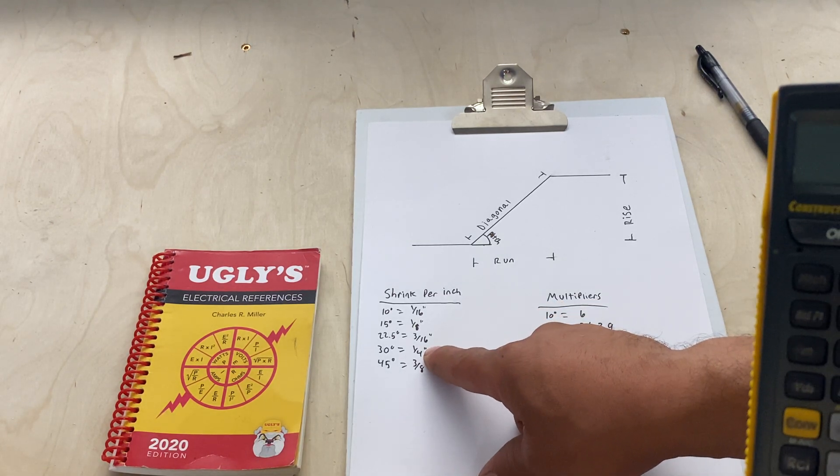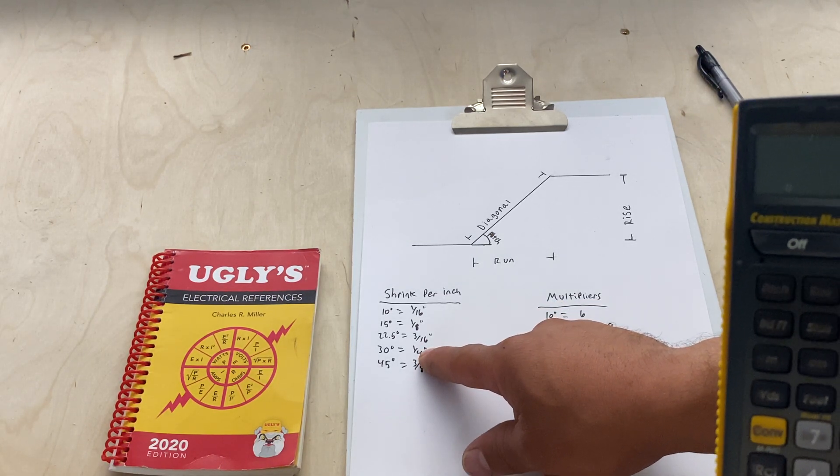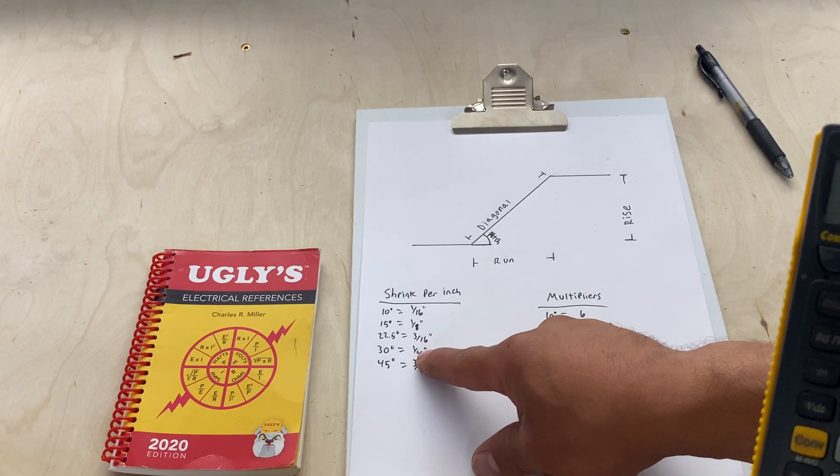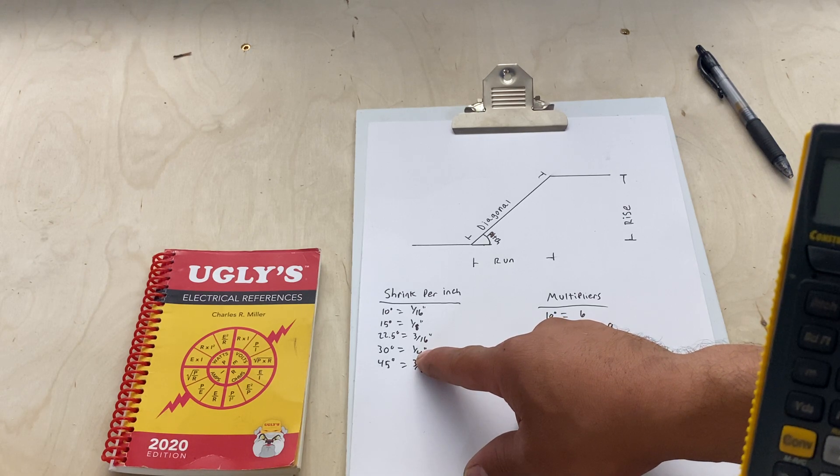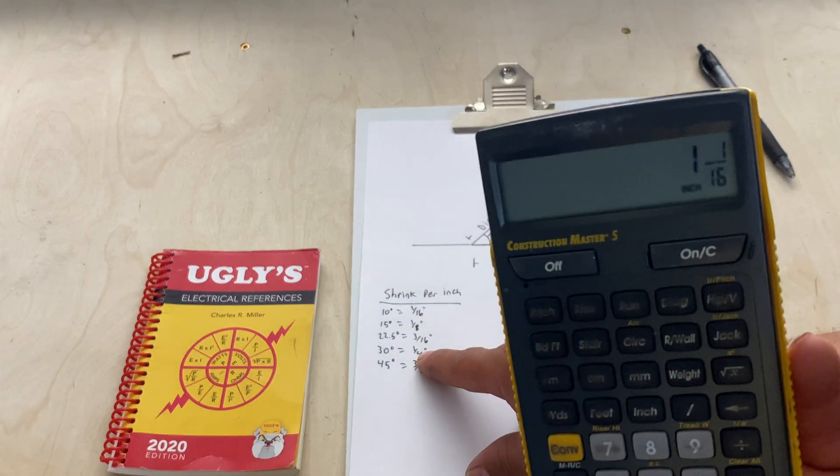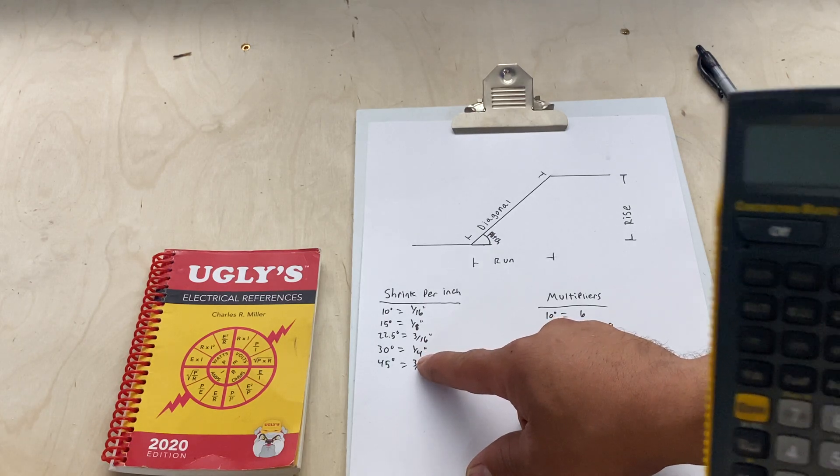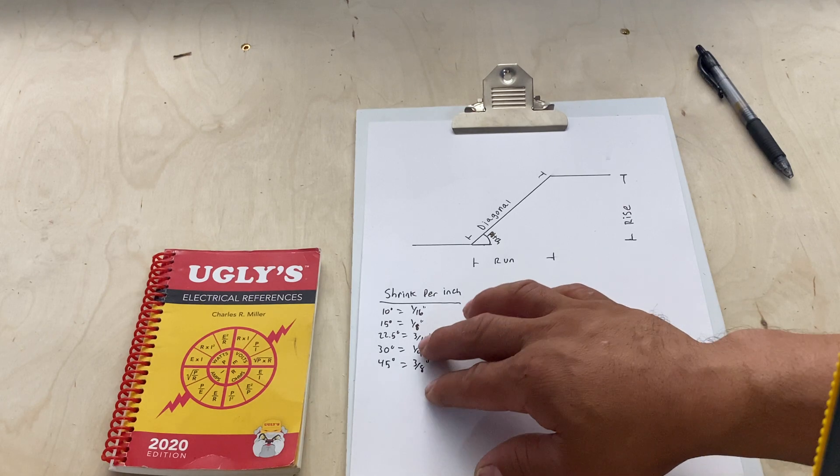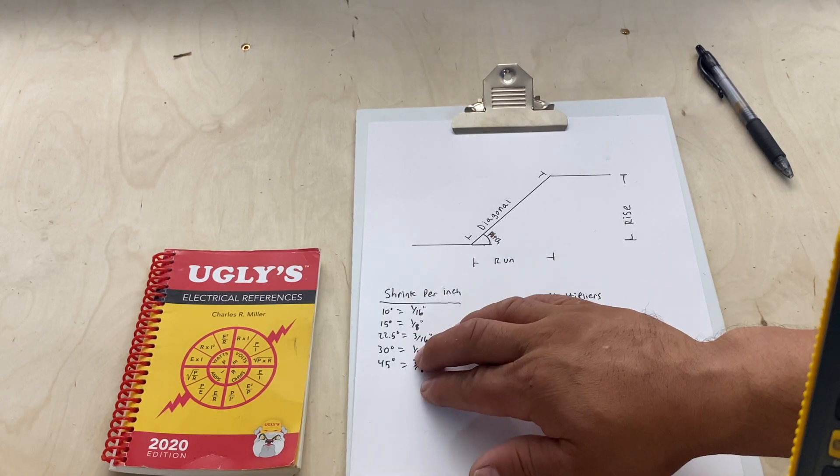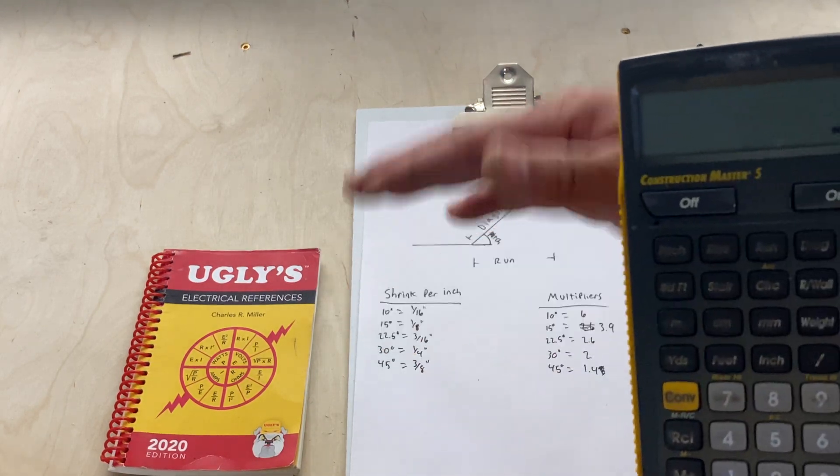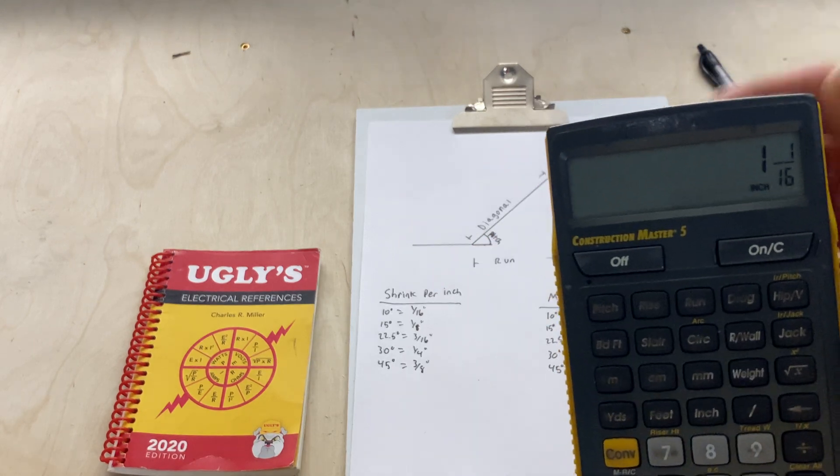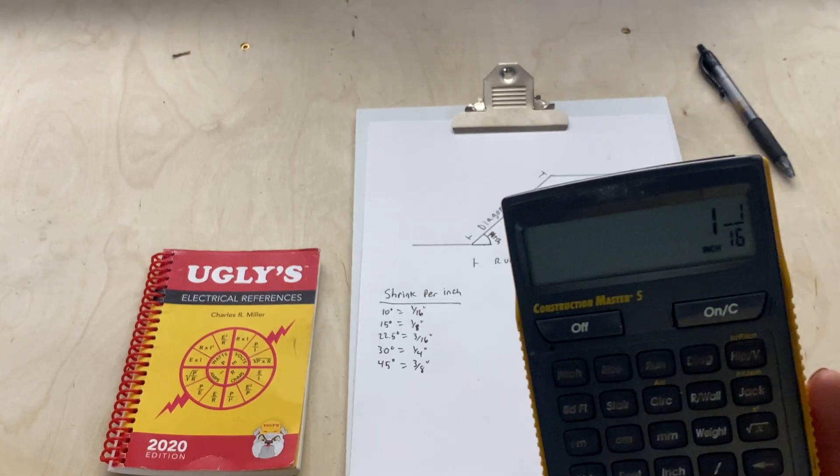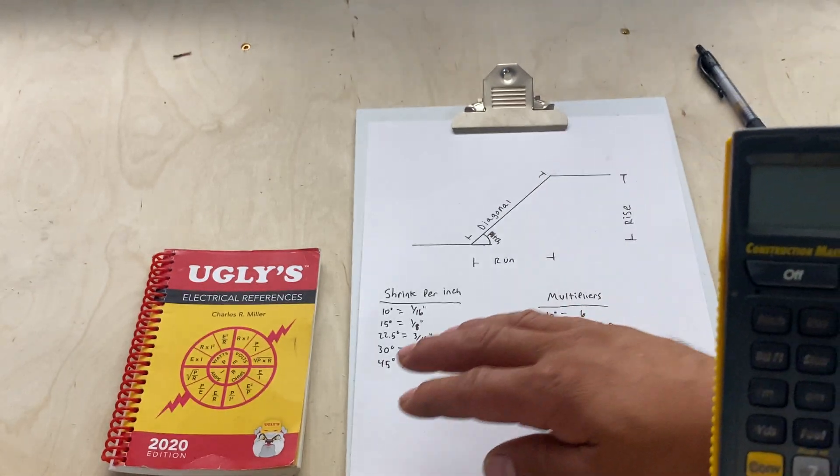We did a four-inch rise at 30 degrees. Four times a quarter should have been one inch. We got one and a sixteenth, it's only a sixteenth more. That's where this comes into play. This gets you by, it's not 100% accurate because the more, the taller the offset, the more it takes into effect. So this calculator is 100% accurate, the chart gets you by.